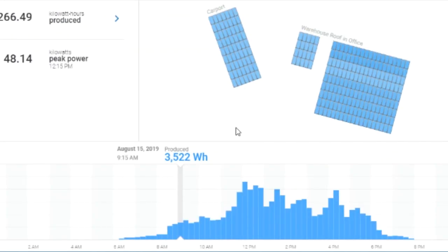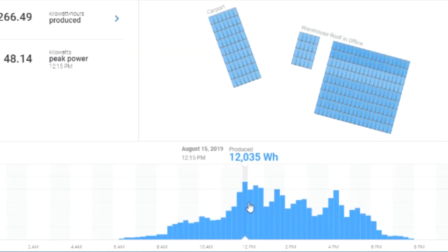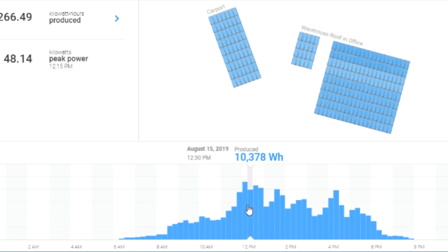And then down here at the bottom, I can see what the system was producing hour by hour. So it looks like we got the most watt hours of production at 12 noon. The system produced 12,000 watt hours or 12 kilowatts.